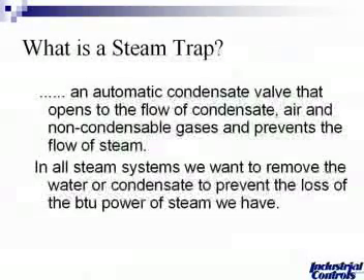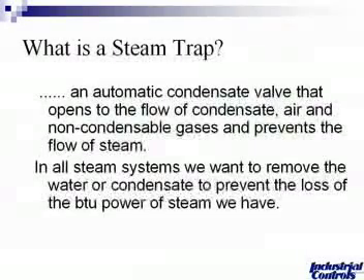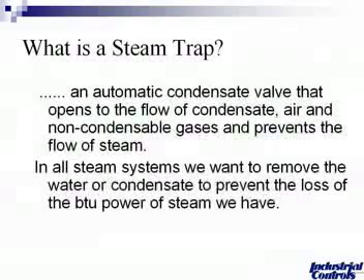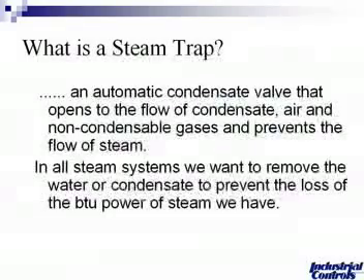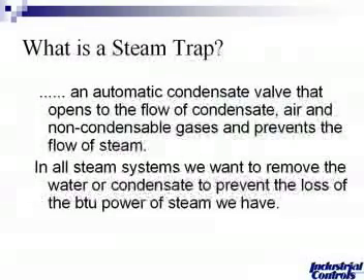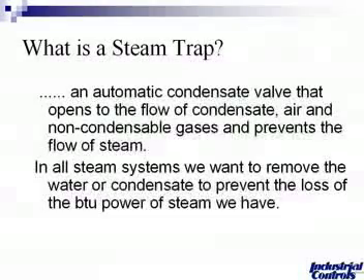What is a steam trap? A steam trap is essentially an automatic condensate valve that opens the flow of condensate, air and non-condensable gases and prevents the flow of steam. In all steam systems, we want to remove the water or condensate to prevent the loss of the BTU power of the steam we have.